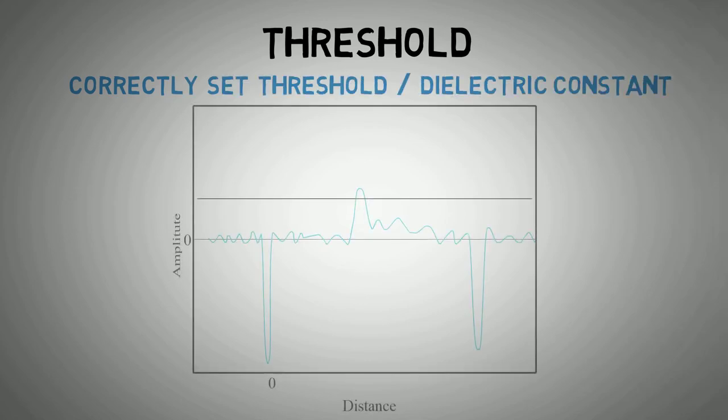The threshold is what determines if a reflection is classed as a level reading or ignored as background by the transmitter. Here is a correctly set dielectric constant and resulting threshold. The threshold is high enough to avoid the noise but low enough to capture the reflection peak caused by the level.